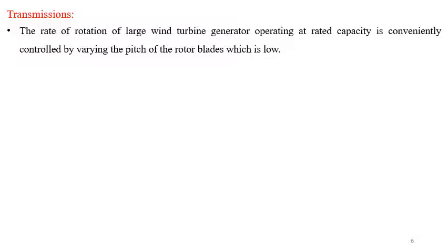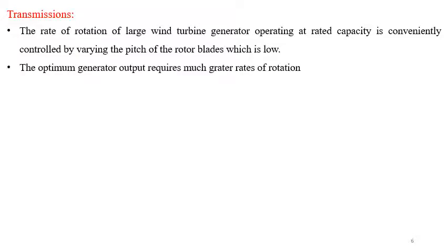So among the transmission options, there are mechanical systems which involve fixed ratio gears, belts and chains, in a single or combination, or hydraulic systems involving fluid pumps and motors, okay. So fixed ratio gears are recommended for top mounted equipment because of their high efficiency, known cost and minimum system risk.